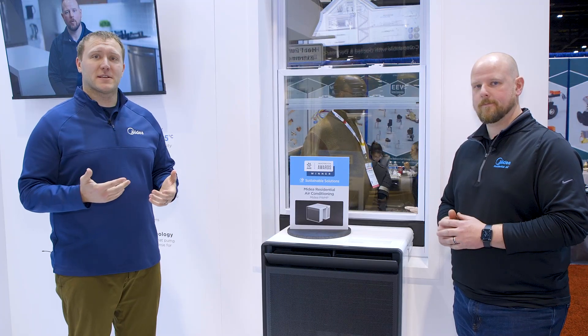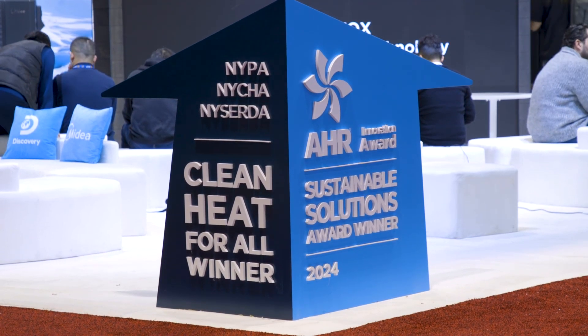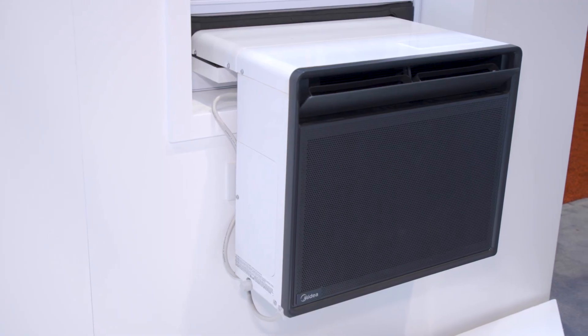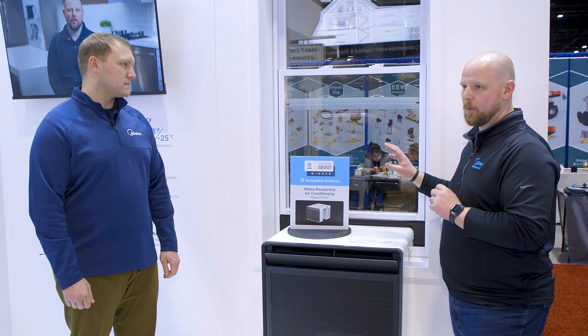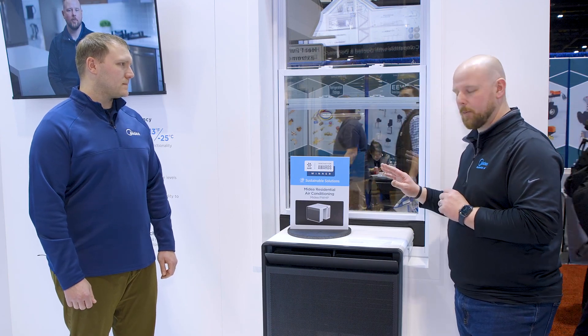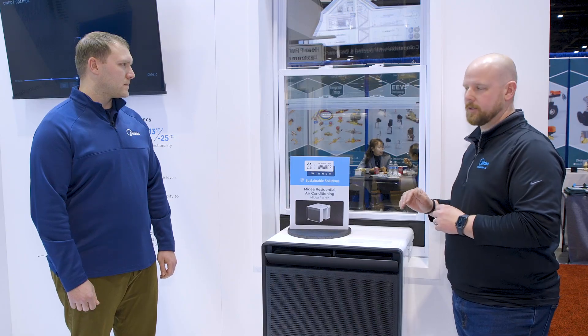I'm here with David Leiser, our retail AC R&D manager, to talk about Midea's PWHP — this year's Sustainable Solutions Innovation Awards winner for 2024 AHR Expo. What we have here is Midea's brand new PWHP, which is a packaged window heat pump. This came about from New York City's Clean Heat for All Challenge, where the New York City Housing Authority is trying to transition towards electrification, moving away from steam heat towards a window-mounted high-efficiency air source heat pump. We won 20,000 of the 30,000 bid for that challenge. It's a 9,000 BTU per hour heating and cooling unit, high efficiency, with capability down to 5°F with 100% heating and functionality all the way down to negative 13°F. It's a 115-volt, 15-amp unit, so it plugs right into the wall just like a normal window AC — no electrical upgrades required. It's also meant to be installed fully from the inside: the outside rotates flat, you install it onto the mounting bracket, slide it in, it rotates in place, you seal it up, and you're good to go.